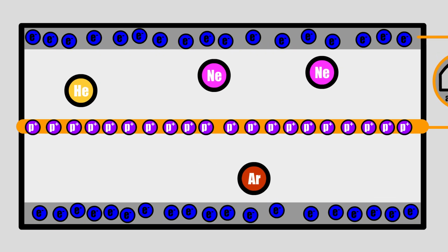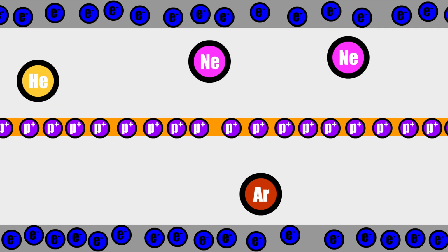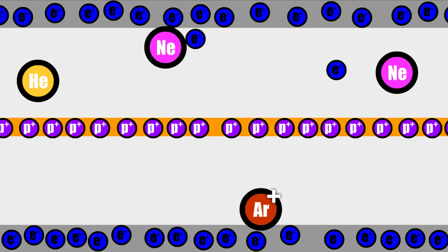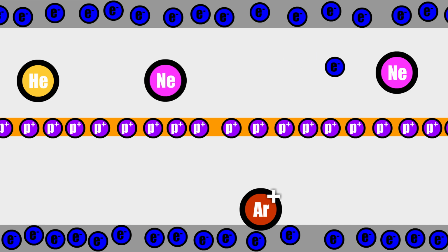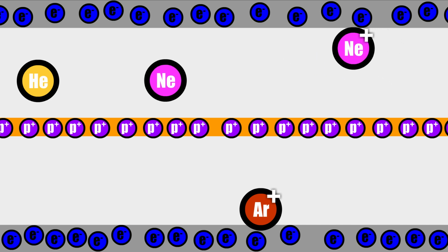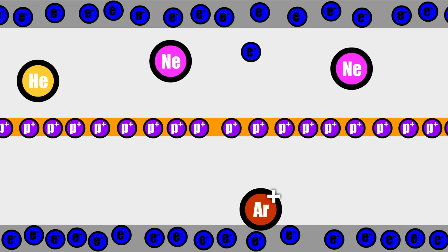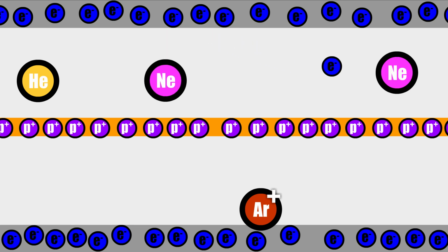One side of the Geiger tube is covered with glass. Radiation entering from here hits the noble gases that are abundantly present inside the tube and ionizes them with its energy. The ionized noble gas is positively charged and is attracted by the negatively charged shell. The electron resulting from ionization is attracted by the positively charged rod at the center.